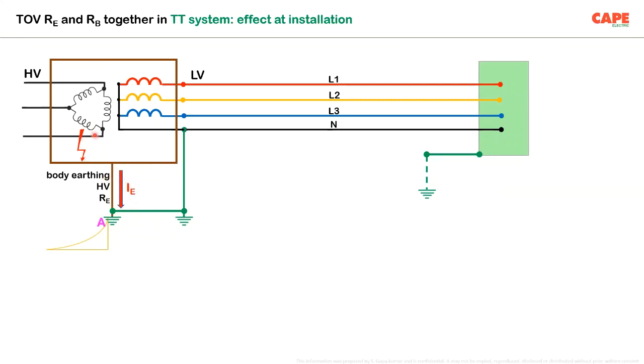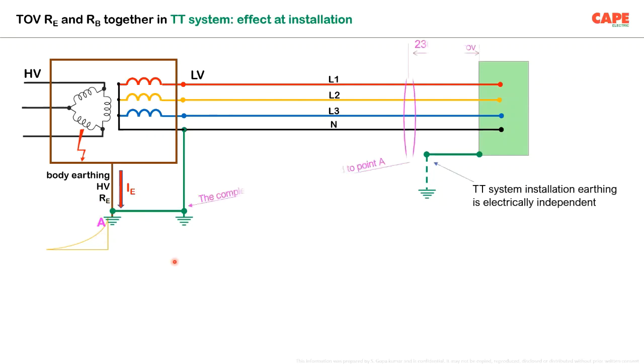Whenever there is a fault on the transformer high voltage system, once the fault current goes through this particular earth electrode on the ground, a voltage gradient is created. Now, the important point you should think is the complete low voltage electrical supply is referenced to the neutral, and the neutral is connected to the point with which the high voltage fault is dissipated, which is having a potential gradient. So what happens is the phase and the neutral is referenced to a point A.